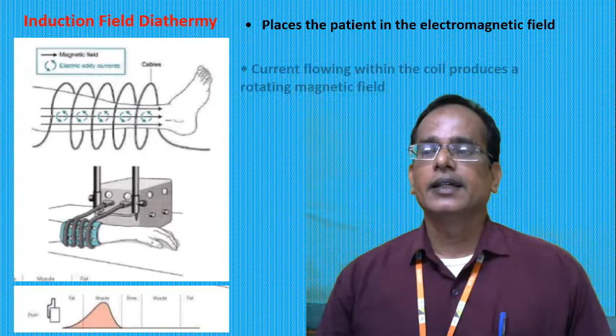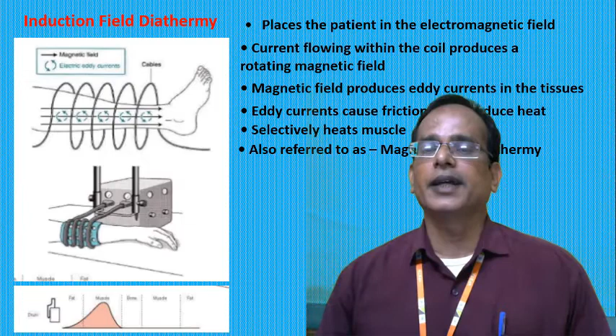Third one, the magnetic field produces eddy current in the tissues. So by that way the heat is generated. The eddy current causes friction that produces heat, and it selectively heats the muscles. So particular muscles must be relieved, meaning they are winding the coil on that particular portion. So this is the one. This is also called a short wave inductive field diathermy. Another name is magnetic field diathermy.